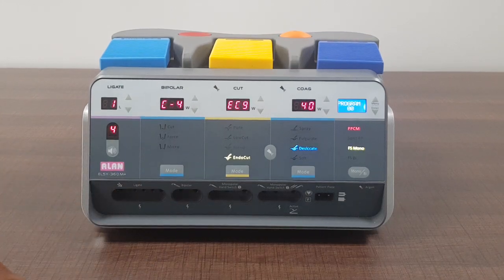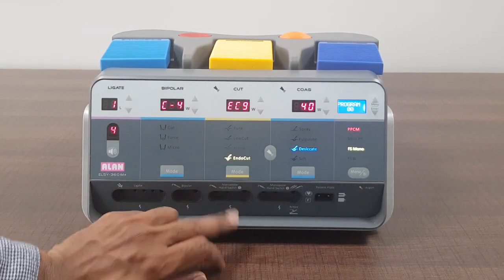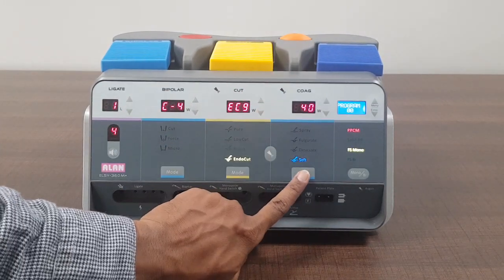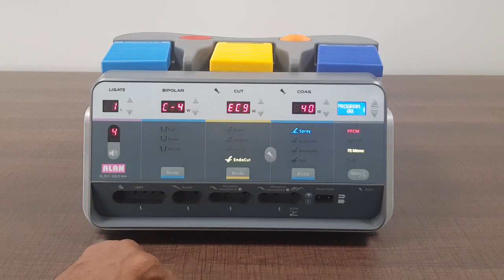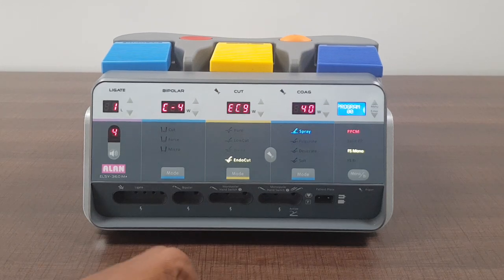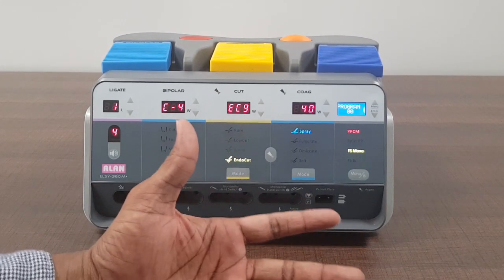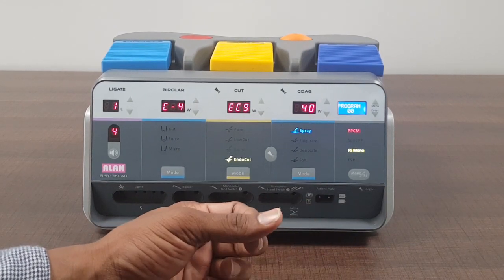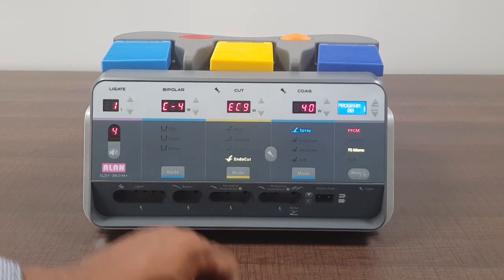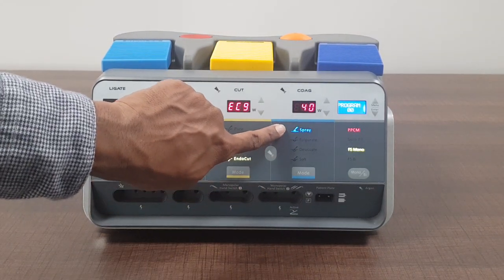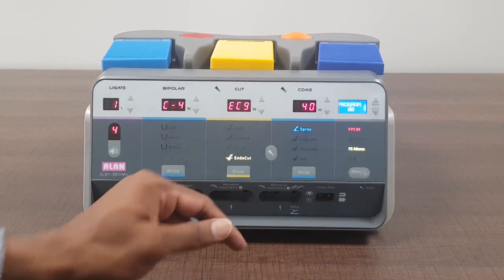So that was monopolar cut. Now coming to monopolar coagulation. We have six modes in monopolar coagulation, which means six different features using which you can coagulate for different type of tissues, different type of scars and tissue resistance. First one is spray. Spray means it is a non-touch coagulation.